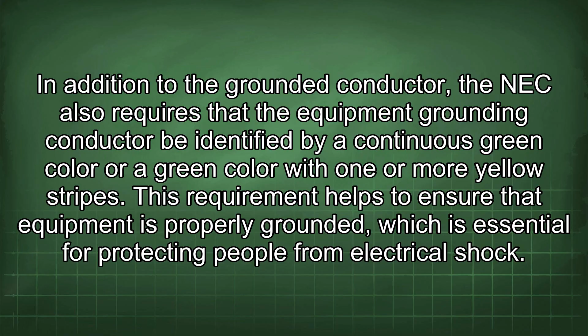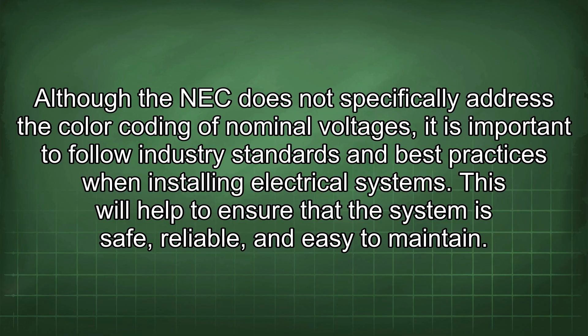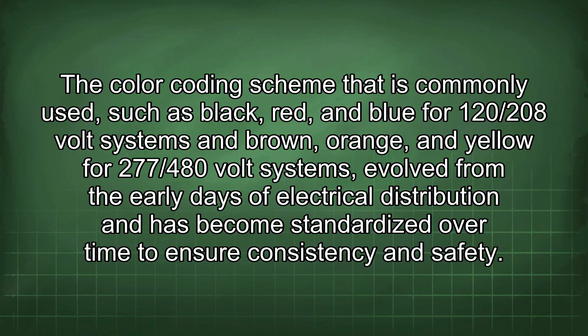Although the NEC does not specifically address the color coding of nominal voltages, it is important to follow industry standards and best practices when installing electrical systems. This will help to ensure that the system is safe, reliable, and easy to maintain. In summary, the color coding of nominal voltages is not specifically addressed in the NEC. However, industry standards such as ANSI/NEMA WC 3.2022 and IEEE Std 141.2019 provide guidelines for this practice. The color coding scheme that is commonly used, such as black, red, and blue for 120/208 volt systems and brown, orange, and yellow for 277/480 volt systems, evolved from the early days of electrical distribution and has become standardized over time to ensure consistency and safety. It is crucial to follow these standards and best practices when installing electrical systems to ensure their safety, reliability, and ease of maintenance.